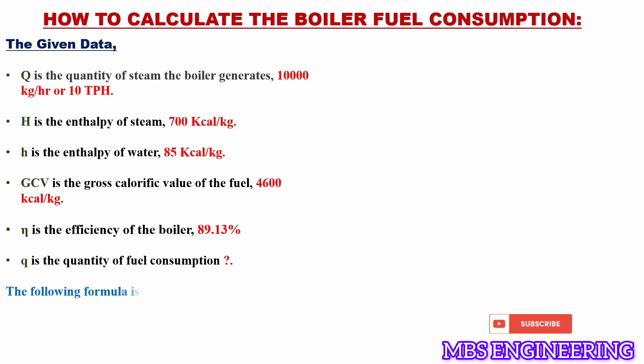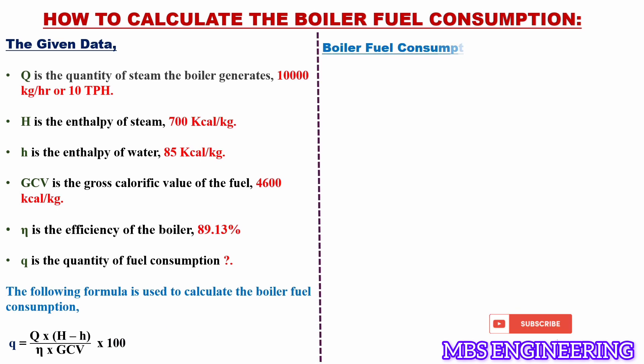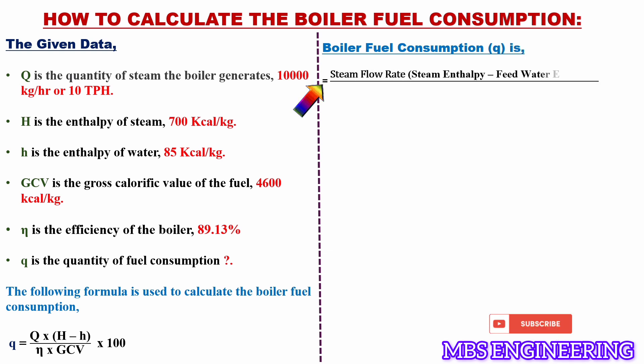The following formula is used to calculate the boiler fuel consumption: small q equals capital Q into (capital H minus small h) into 100, divided by eta into GCV. Or equivalently, q equals the steam flow rate multiplied by (steam enthalpy minus feed water enthalpy) into 100, divided by the boiler efficiency into the fuel gross calorific value.